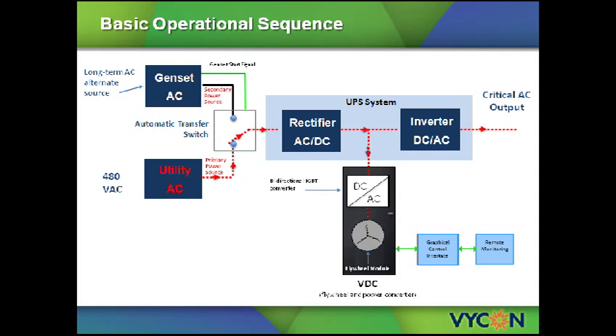This simplified one-line diagram demonstrates the operational sequence of the continuous power system when utilizing Vycon's flywheel energy storage system. In normal operation, power for the critical load is supplied from the utility source. For three-phase power applications in the United States, this is typically at 480 VAC. The utility source feeds into the primary source side of the ATS.